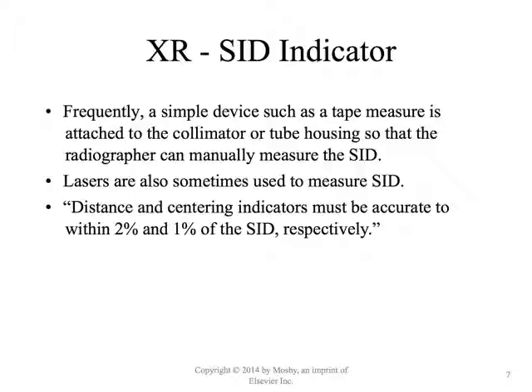Very similar when they're doing that centering indicator, they will make a 10 centimeter square box and they are going to X-ray directly onto a flat plate ion chamber and they're going to see, is it incident with the area that we said it was within? Is it within that 10 centimeter square box by at most, it can be no more than 1%. All right, so it has to be very, very accurate.